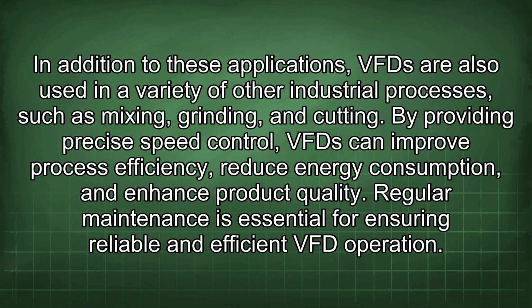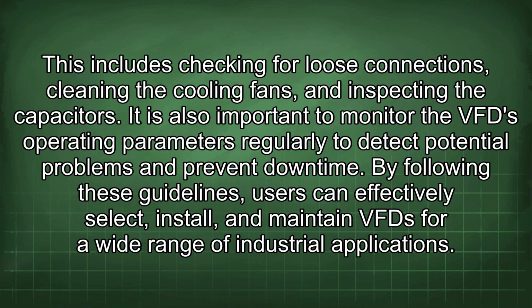In addition to these applications, VFDs are also used in a variety of other industrial processes such as mixing, grinding, and cutting. By providing precise speed control, VFDs can improve process efficiency, reduce energy consumption, and enhance product quality. Regular maintenance is essential for ensuring reliable and efficient VFD operation. This includes checking for loose connections, cleaning the cooling fans, and inspecting the capacitors. It is also important to monitor the VFD operating parameters regularly to detect potential problems and prevent downtime. By following these guidelines, users can effectively select, install, and maintain VFDs for a wide range of industrial applications.